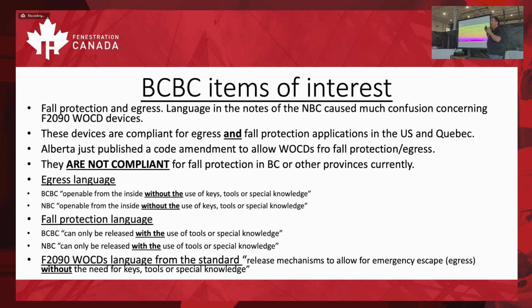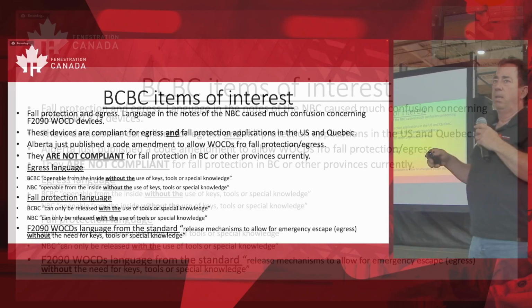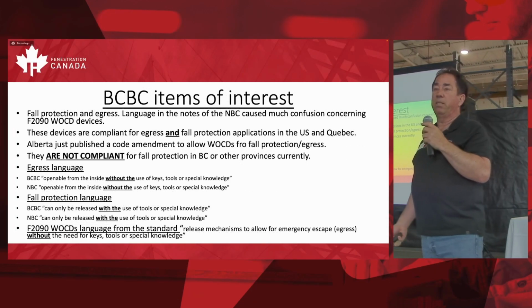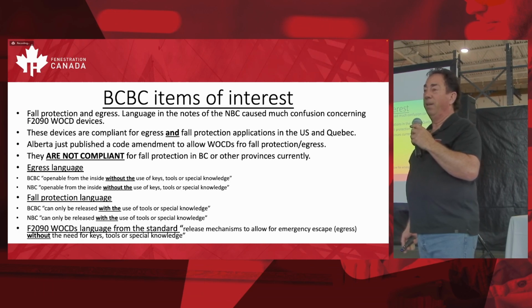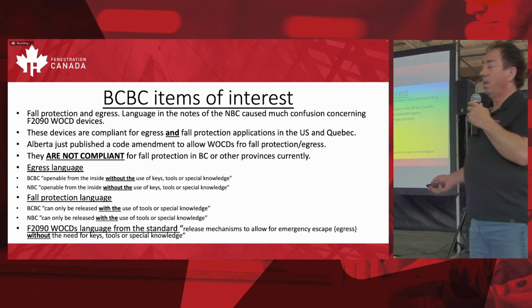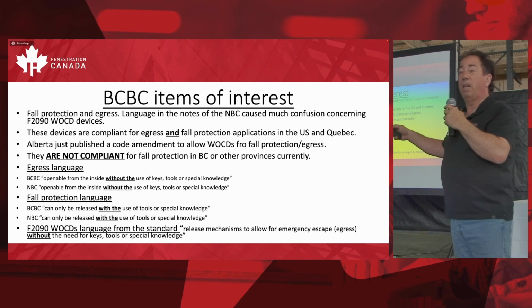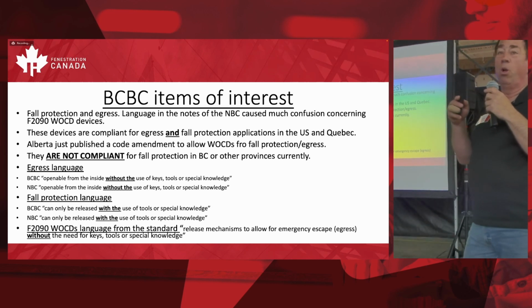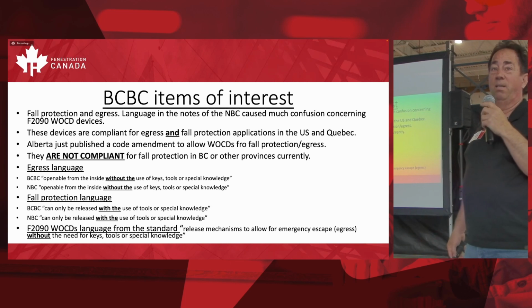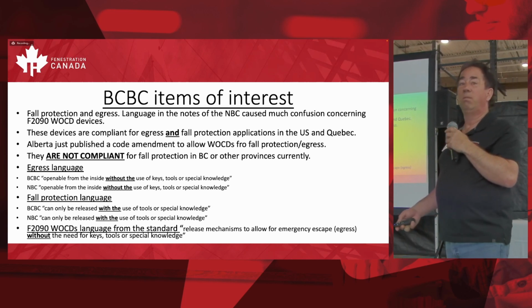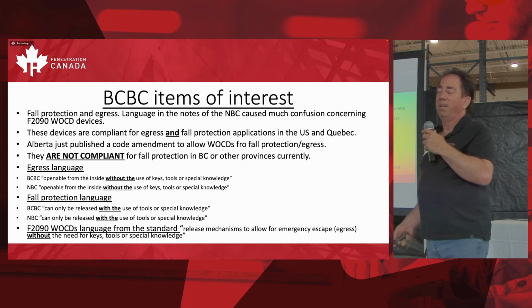Assa Abloy was there, and they have one of these devices that they're trying to get compliant or accepted. But again, it's tested under the F2090 standard, and as soon as that happens, that language comes into play and makes the device non-compliant. So in my discussion with them, I said, why don't you take that device you've tested and make a very small change to it, don't test it, and say it no longer falls under that language. They're thinking about it.